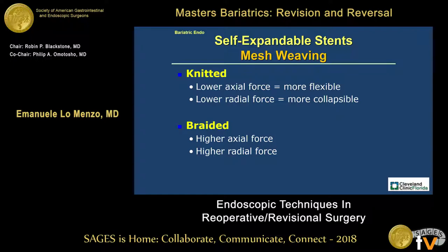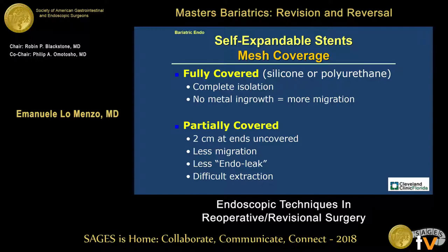The mesh of the stent has particular characteristics. In general, in order to have more flexibility, we want mesh in the stent that is knitted as opposed to braided. In the choice of stent, we have to decide between a fully covered stent or a partially covered stent. The fully covered stent completely isolates the leak, but the absence of ingrowth equals more migration, as opposed to a partially covered stent, which decreases what we could call an endoleak but is much more difficult to extract over time.